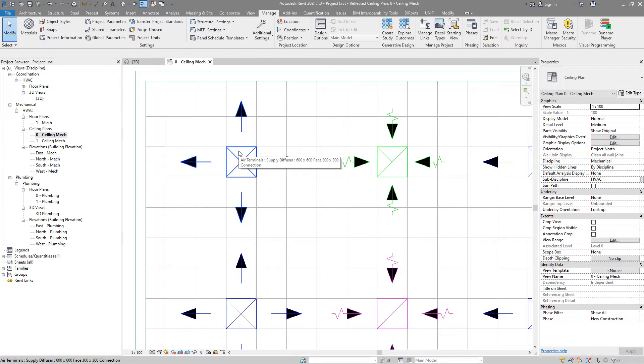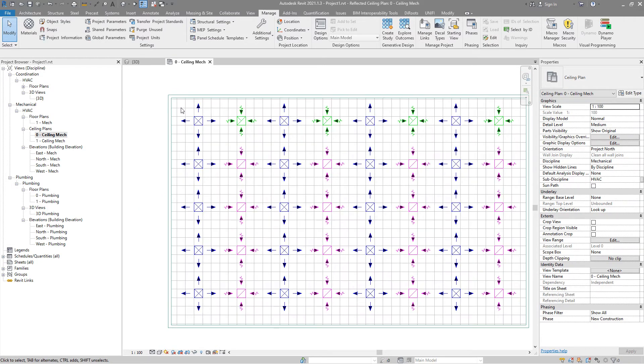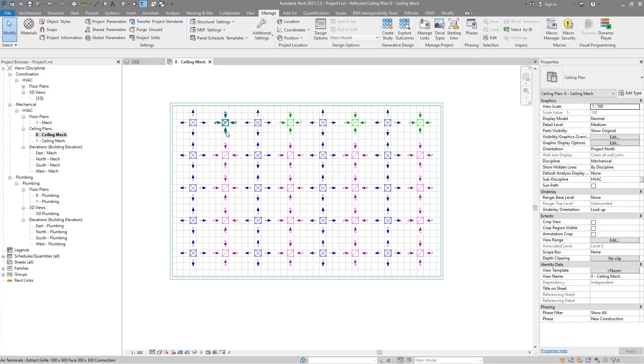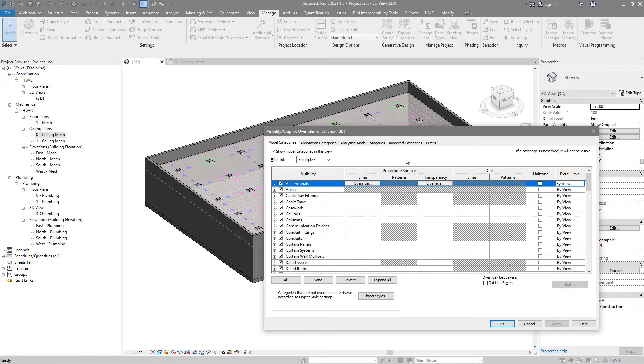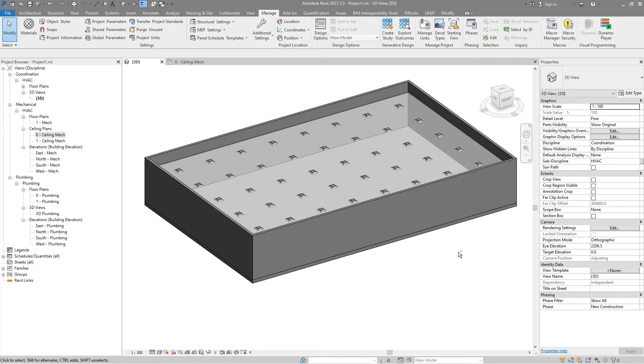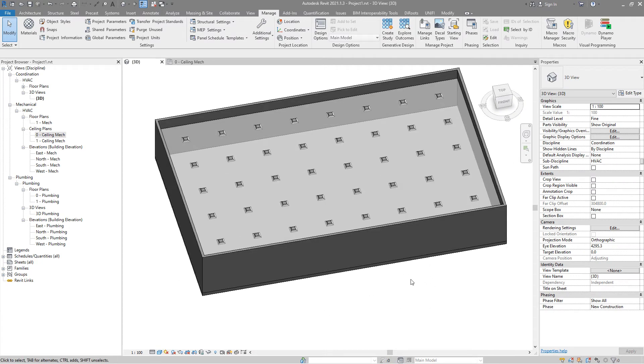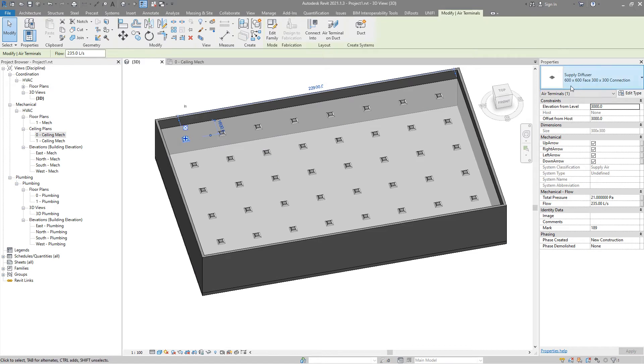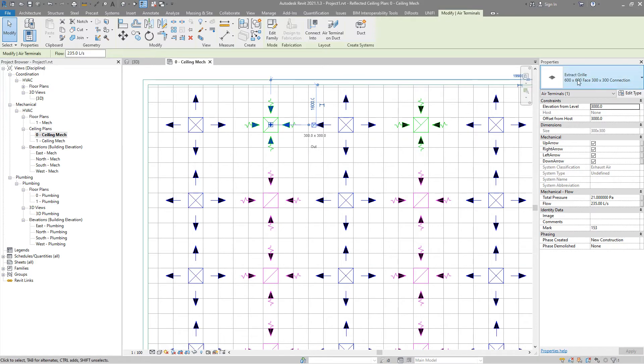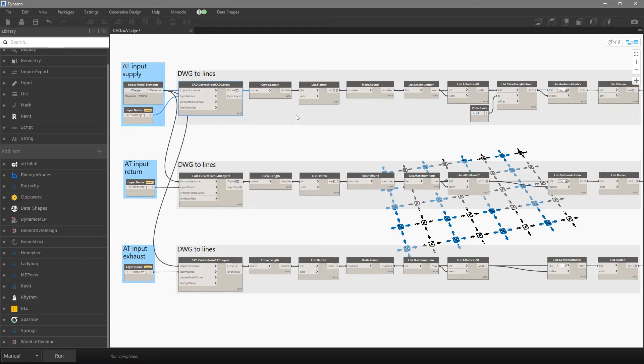Once we recognize those lines, we go to the middle point of each line to know the center position of each element. Then we choose which family we want for the supply diffuser, for return, and for exhaust. If we turn off the AutoCAD, we can see that Dynamo very quickly and accurately inserted those families — where we need a supply diffuser we have that family, over here it's return, and over here it's exhaust.